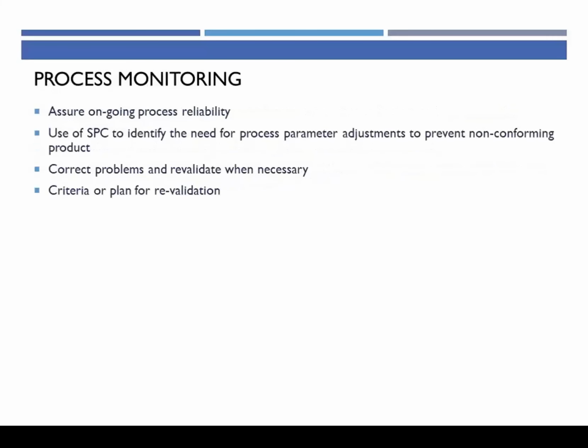So that's the PQ. When you're done with that, the product will be saleable pending other things like design validation and approvals, etc. It doesn't end there, though. Once you've done the PQ, you still have to monitor your process over time to show that it still remains stable and in control. And that means you're still going to have to sample from every batch and use SPC to show that you're staying in a state of control.